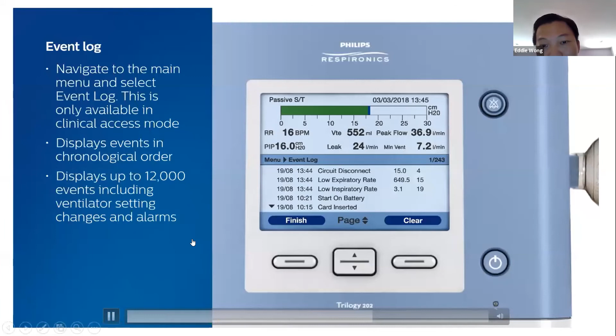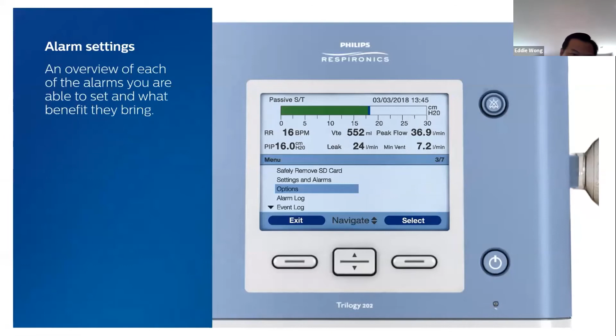Okay, 12,000 events. Including ventilator setting changes and alarms. Here, we will review each of the alarms you are able to set and what benefit they bring to ventilation. The circuit disconnect alarm is a high priority alarm. It occurs when the breathing circuit is disconnected, has a large leak, or if the patient airway is completely occluded.